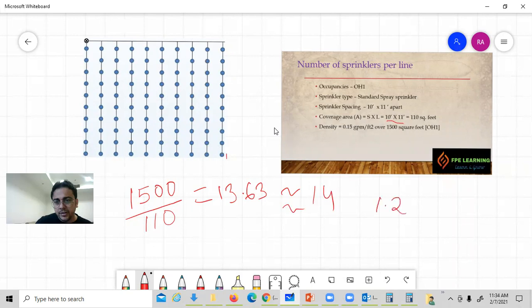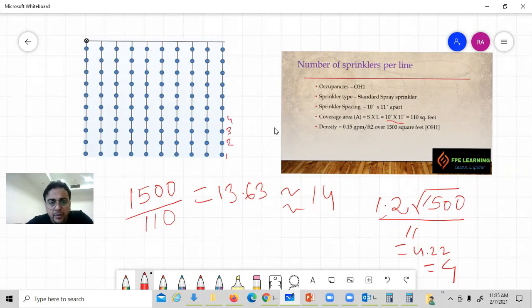With this formula, the maximum distance over 11 feet spacing between sprinklers is 4.22. So maximum number of sprinklers required, we will consider 4. We will start from here. This is our node number one, node number two, three, and four.